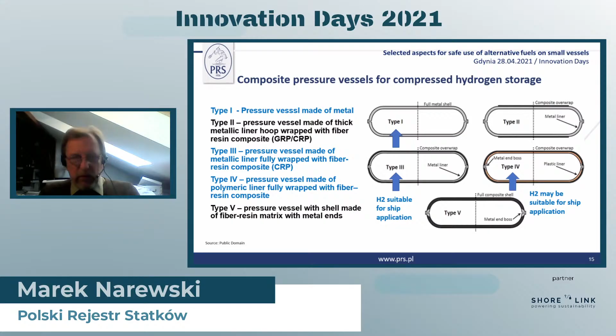Of course, you can use a metal cylinder, type 1. You can use a type 4 cylinder, which is of quite similar design to type 3, but the liner inside is made of plastic. In the type 3 cylinder, the liner is made of metal. So it's much better in terms of protection against hydrogen embrittlement and permeation, which could be a problem. This is a safe place for hydrogen, and some guidance could be taken for other low flash point fuels. As was discussed earlier, consider placement of hydrogen cylinders on a pusher.